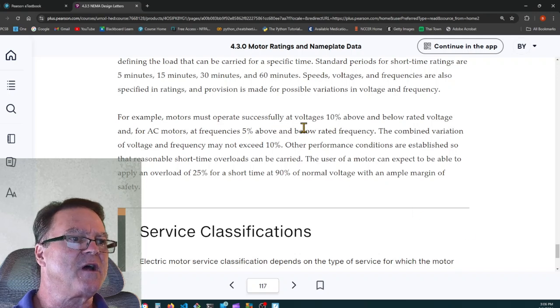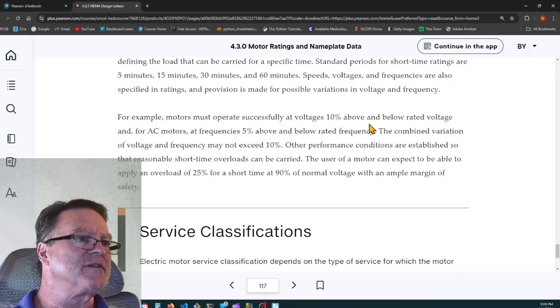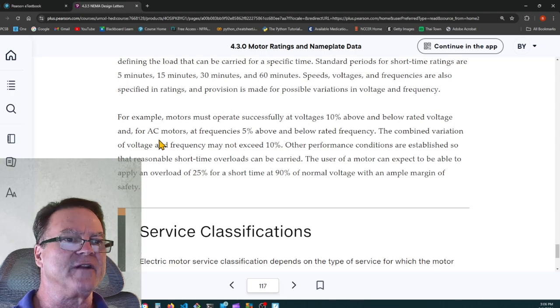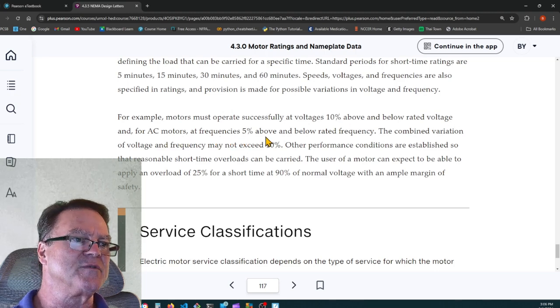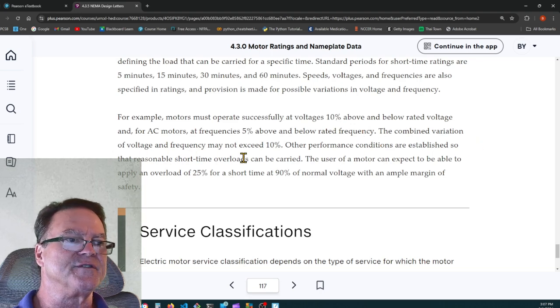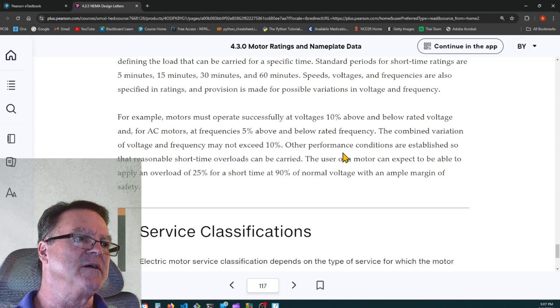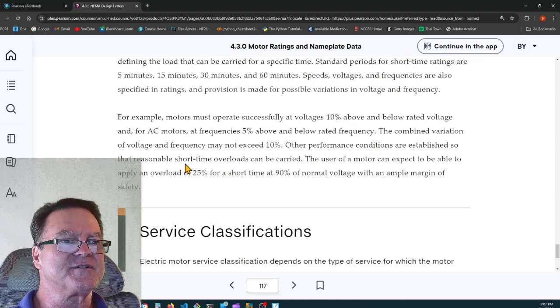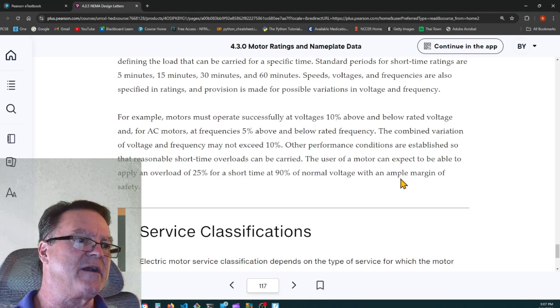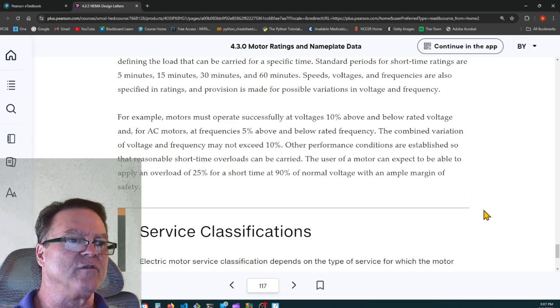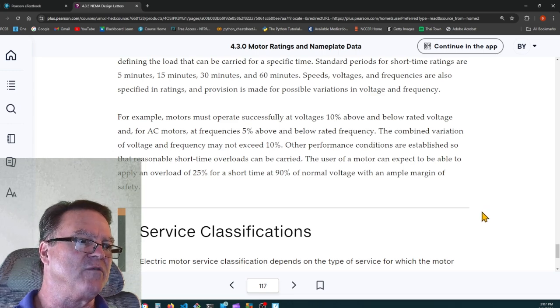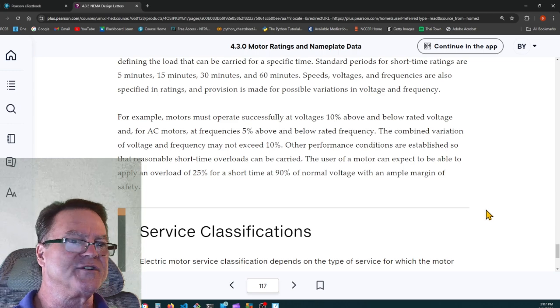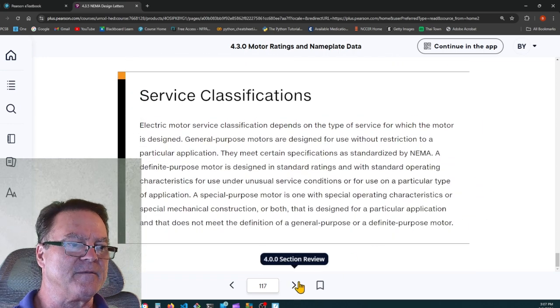All right. So motors must operate successfully at voltages 10% above and below the rated voltage, and for AC motors at frequencies 5% above and below rated frequency. The combined variation of voltage and frequency may not exceed 10%. Other performance conditions are established so that reasonable short time overloads can be carried. The user of a motor can expect to be able to apply an overload of 25% for a short period of time at 90% of normal voltage with an ample margin of safety. Okay.